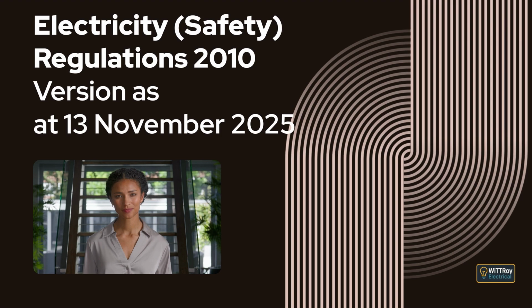The regulation also explains that a person reconnecting or restoring supply is entitled, if acting in good faith, to rely on a written confirmation from the owner that no general or high-risk prescribed electrical work has been done since disconnection. It finishes by explaining that failing to comply with these requirements is an offence and carries a Level 2 penalty. This part covers certifying installations.